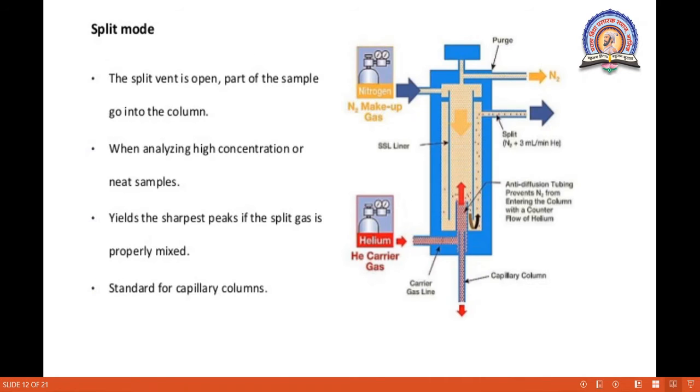Okay, then we start with the first injector, that is the split injector, or we simply say split mode. In this case, the split vent is open. Part of the sample goes out this side. Split injectors are most commonly used when we analyze a high concentration or neat sample. Neat sample means a sample which is not dissolved in any solvent; directly used samples are called neat samples.